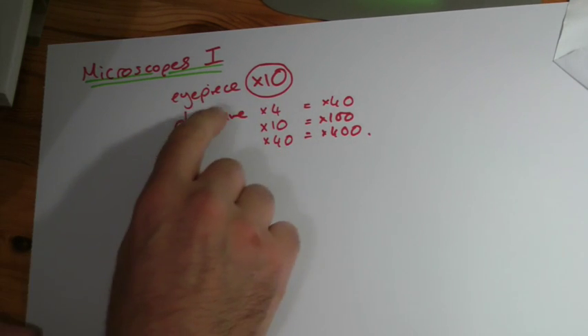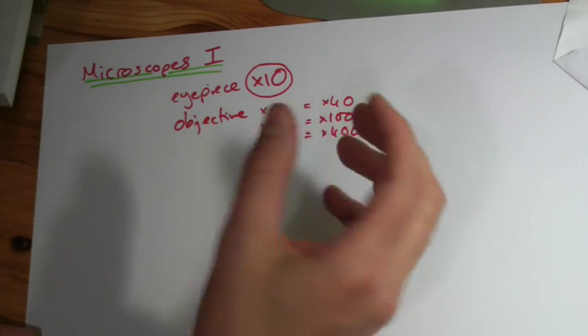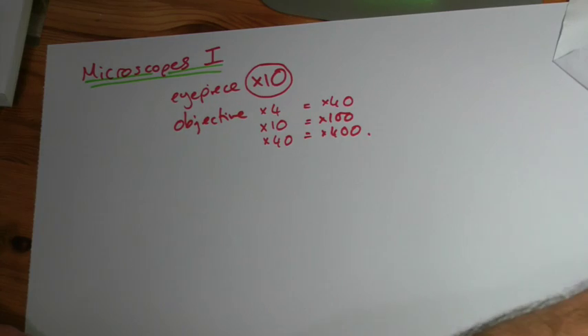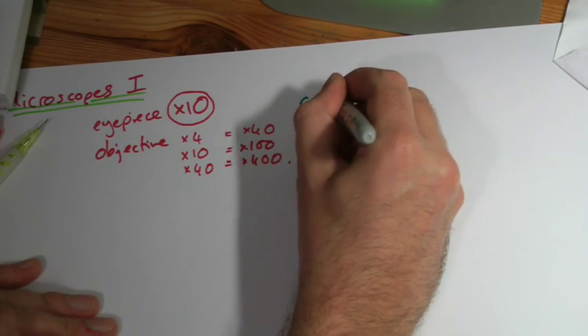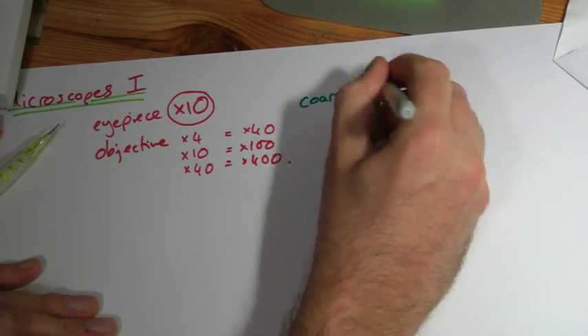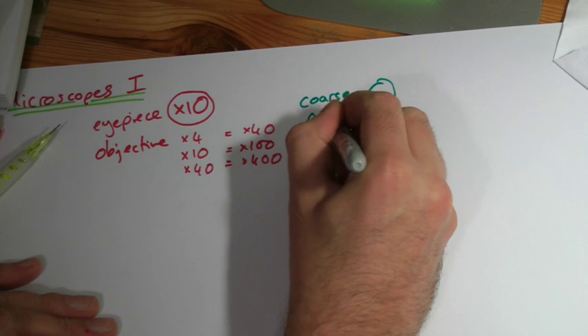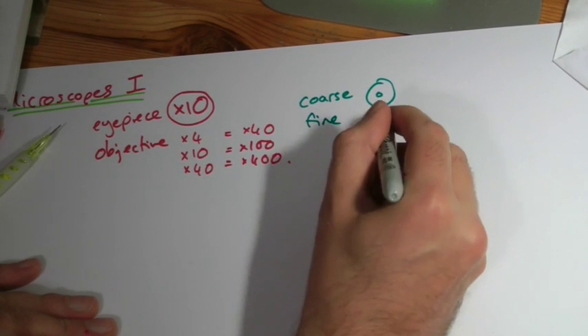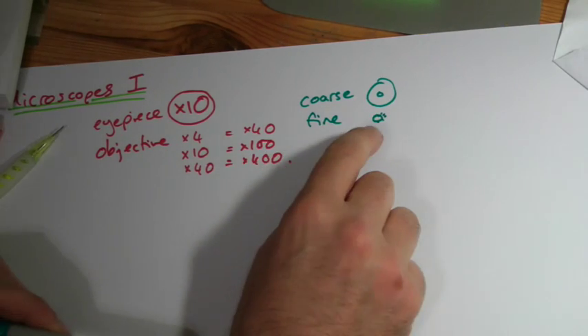You would always start focusing using the lowest objective lens first, it'll be the easiest to get the focus on. You'll then use the two focusing knobs, which are the coarse one, which is the bigger one of the two, so you can wind your way down quickly. And then the fine focusing one, which will be the smaller one, sometimes it even has a little scale on it, which will allow you to zoom in a little bit more.